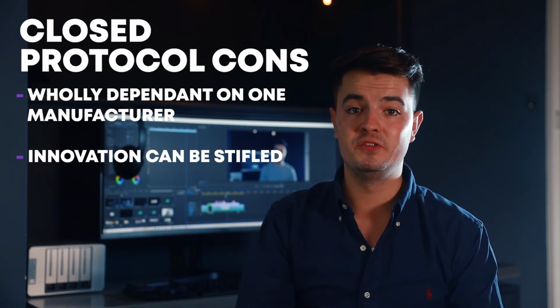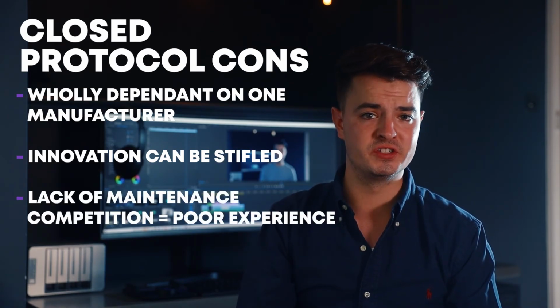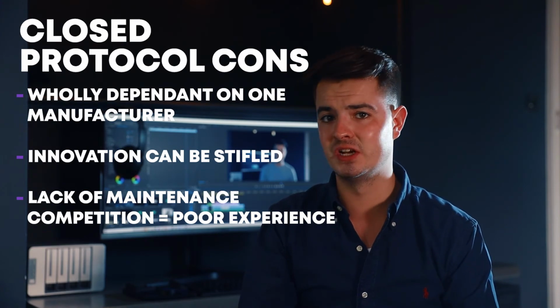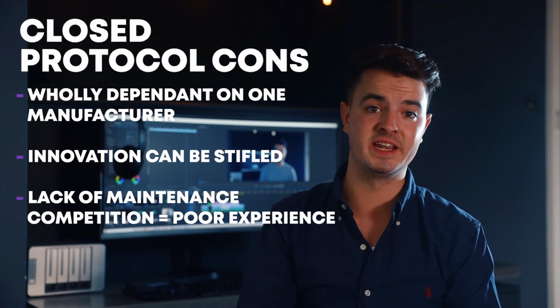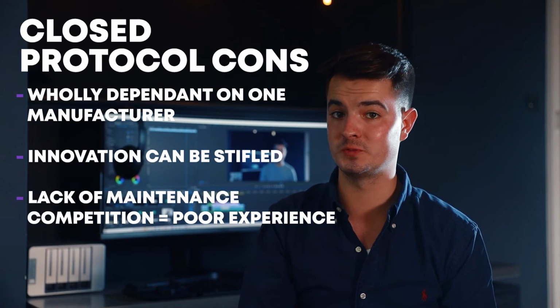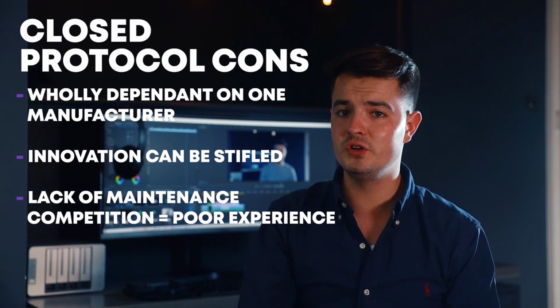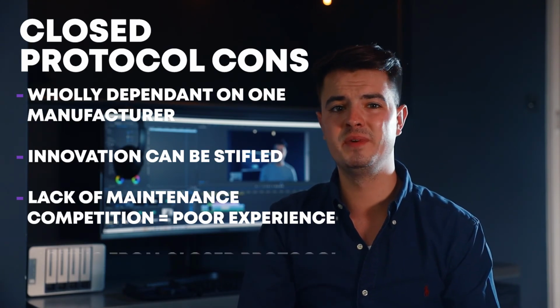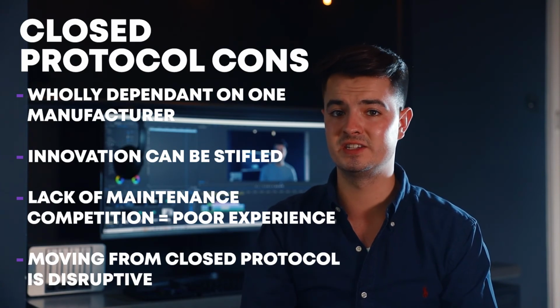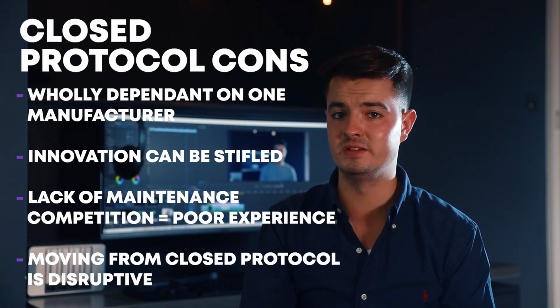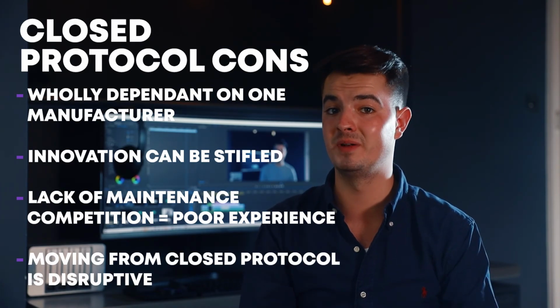Third, closed protocol manufacturers can lack competition for maintenance services, and this can encourage lax service, slow call-out responses, and expensive maintenance contracts which are impossible to get out of. Finally, if you do decide to upgrade or change the system, it can be an expensive and disruptive exercise as the majority of the original supplier's system would have to be removed from the premises and replaced.